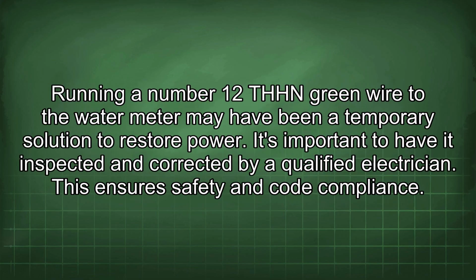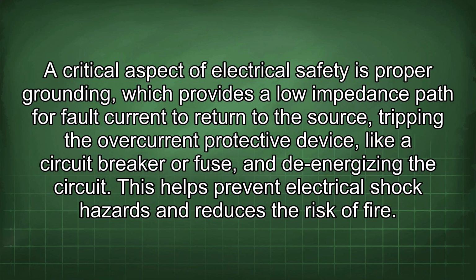Running a number 12 THHN green wire to the water meter may have been a temporary solution to restore power. It's important to have it inspected and corrected by a qualified electrician. This ensures safety and code compliance. A critical aspect of electrical safety is proper grounding, which provides a low impedance path for fault current to return to the source, tripping the overcurrent protective device, like a circuit breaker or fuse, and de-energizing the circuit. This helps prevent electrical shock hazards and reduces the risk of fire.